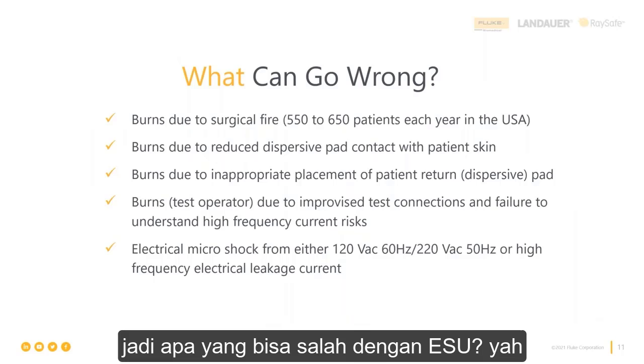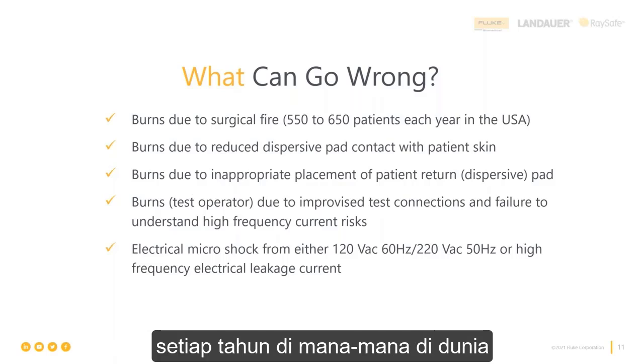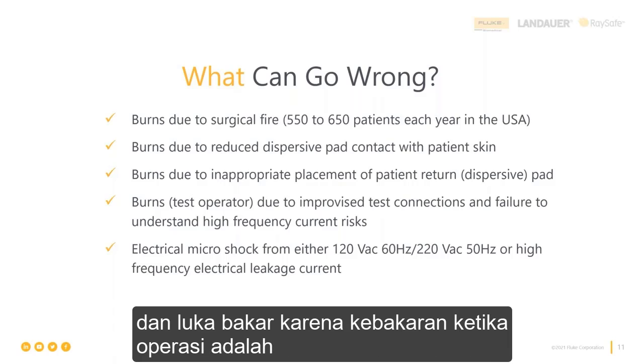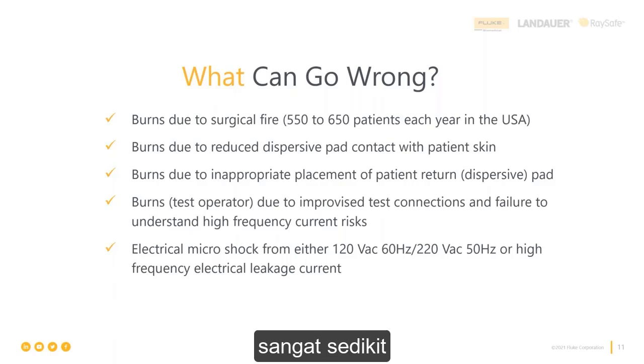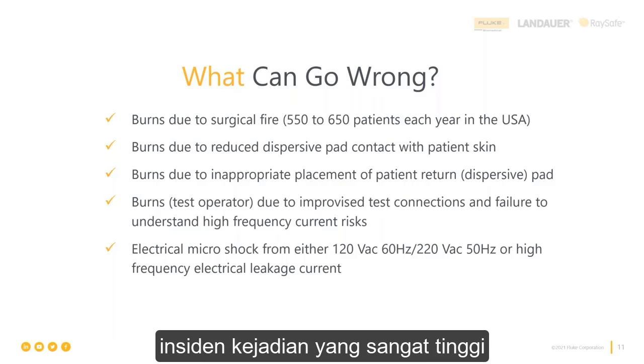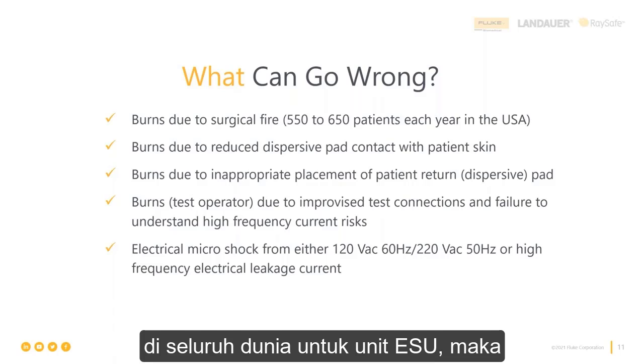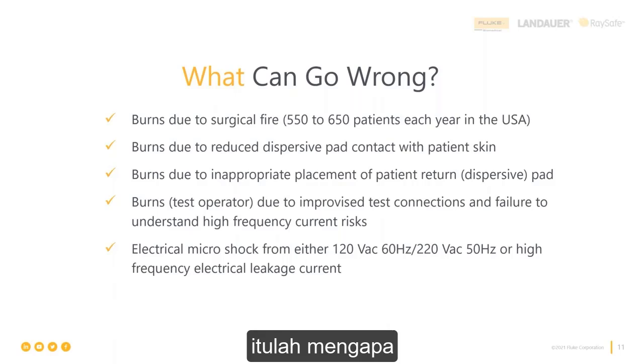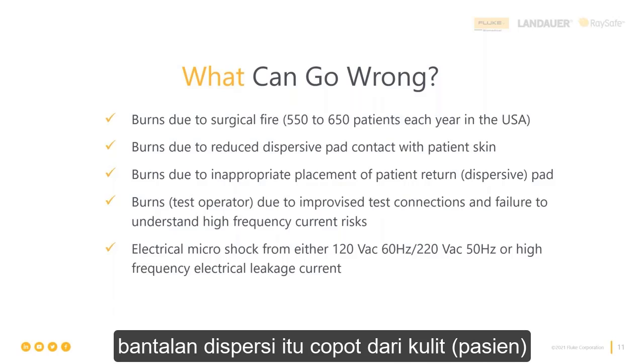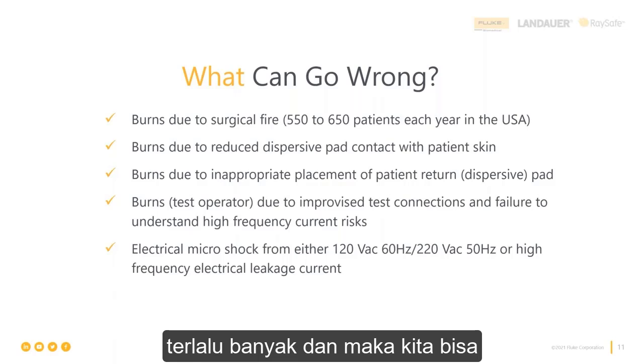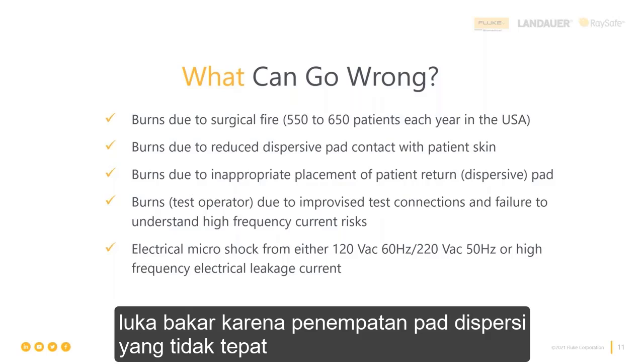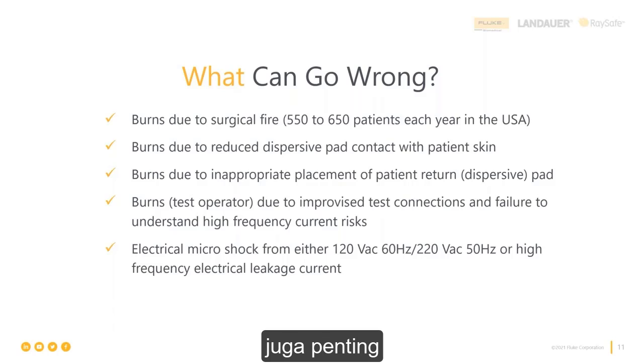So what can go wrong with ESUs? Well, burns still happen every year, everywhere in the world. And burns due to surgical fire are the most severe, although the least typical. Surgical burns not associated with surgical fire are also a very high incidence of occurrence worldwide for electrosurgery units, which is why it's important to make sure we test the contact quality monitor that looks at the dispersive pad, to help us know when the dispersive pad is pulled away from the skin too much, and therefore increase the risk of patient burns because of that. Burns due to inappropriate placement of that dispersive pad or patient return pad are also important.